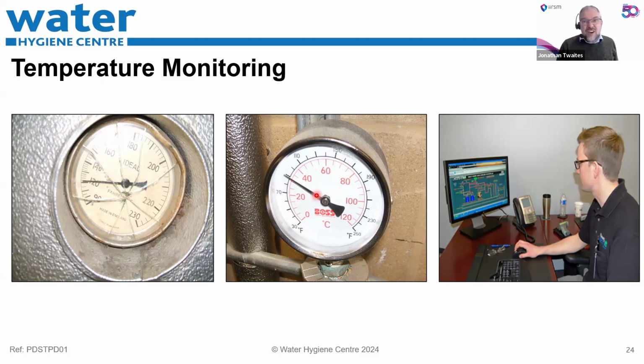They're a good gauge, a good rough indication. So if the gauge on the flow is hovering around 60, it's a good indication that it's on and it's running at the right temperature, but not to be taking our accurate temperature readings. We need our calibrated probes, whether it's our digital probes or infrared guns, calibrated probes to actually take the temperature readings.